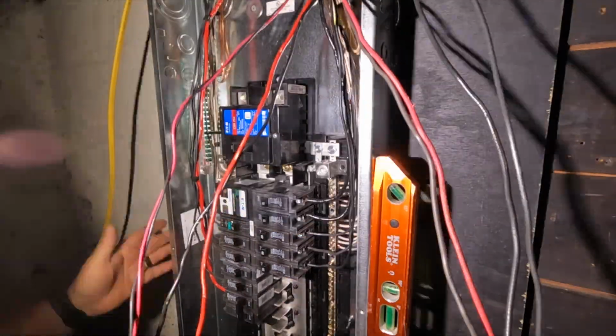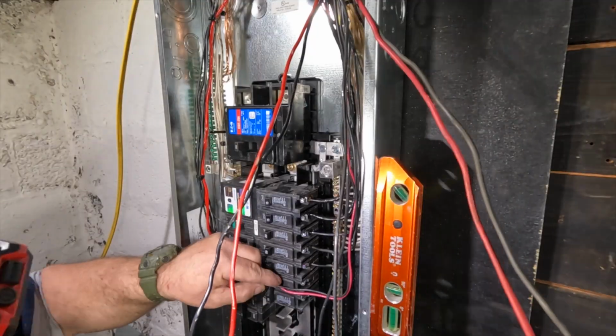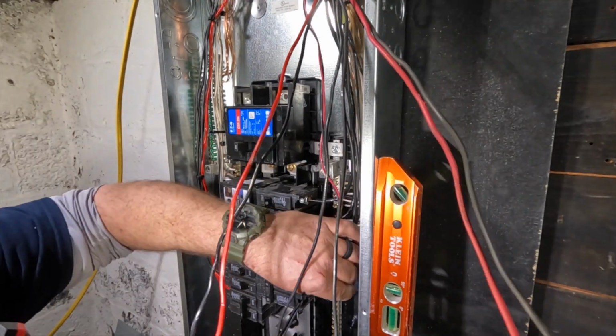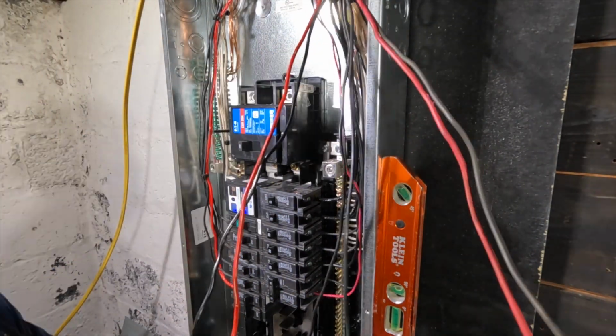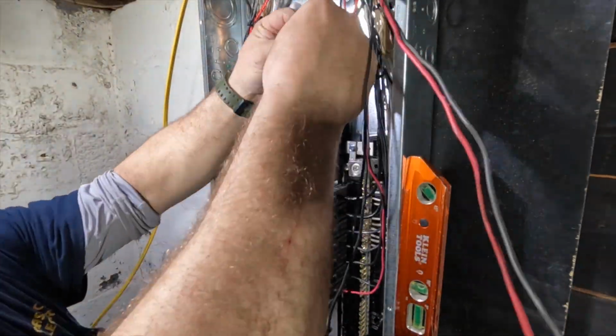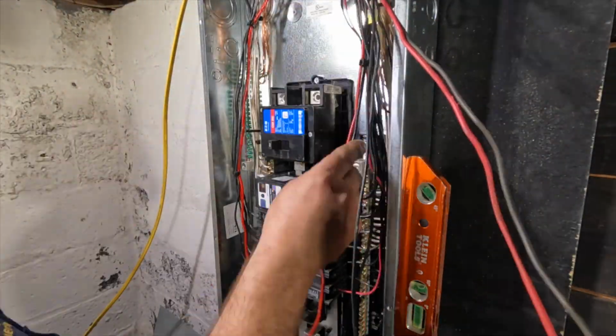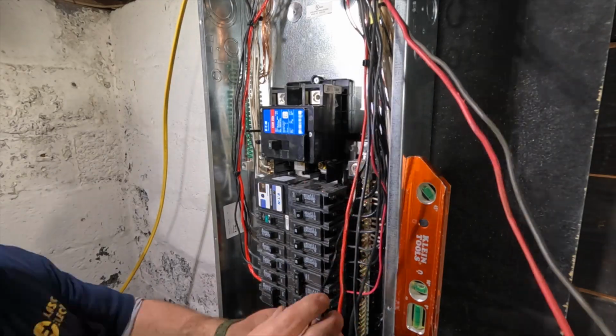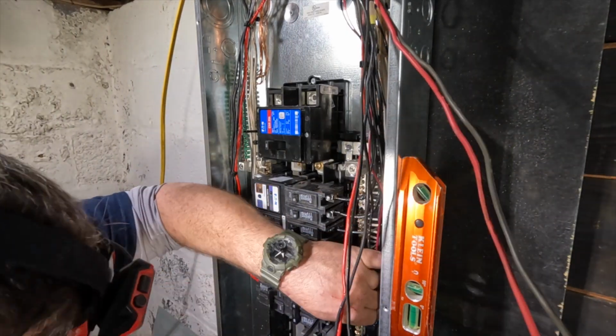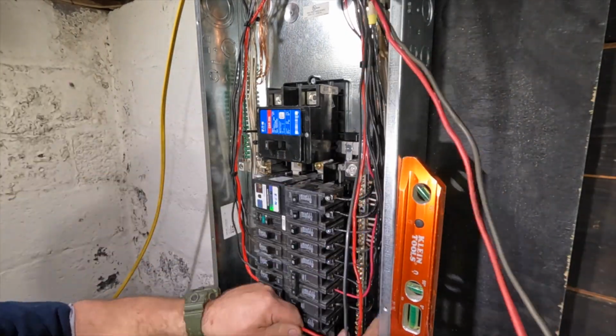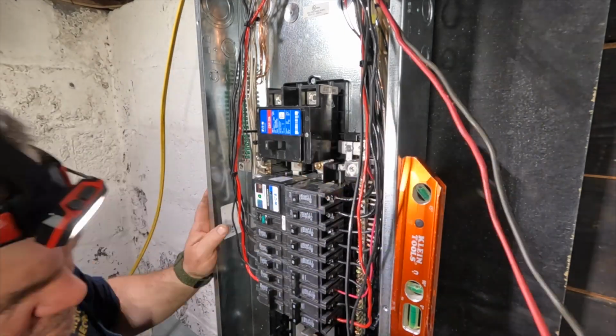Where I put the circuit breakers in the panel really doesn't matter, but one thing I pay attention to during these service upgrades is that there's always a circuit or two that's too short and needs to be extended. So I try to use the home runs, the hot conductors that are shortest, on the first circuit breakers up at the top.